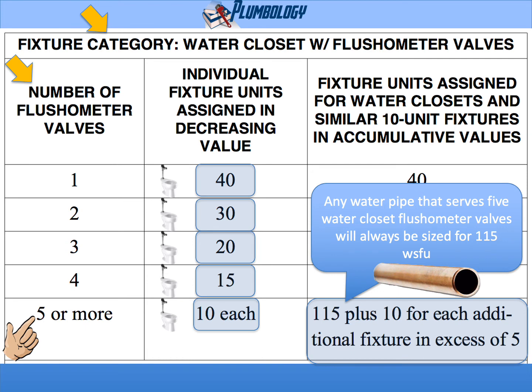So memorize or write down that decreasing scale. For water closet flush valves, it always goes 40, 30, 20, 15, 10. Once you get to 10, everything after it is a 10. So the 6th, 7th, 8th, 9th, 10th flush valve — they're all going to be 10s.